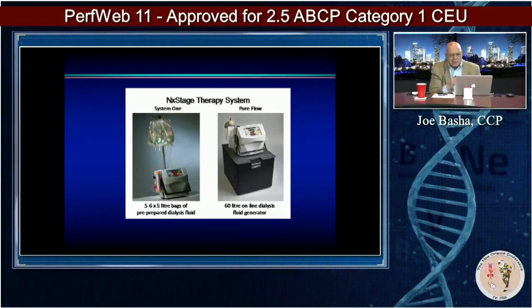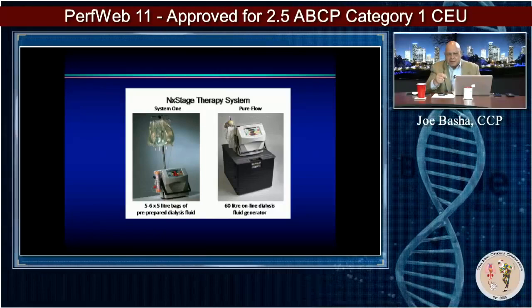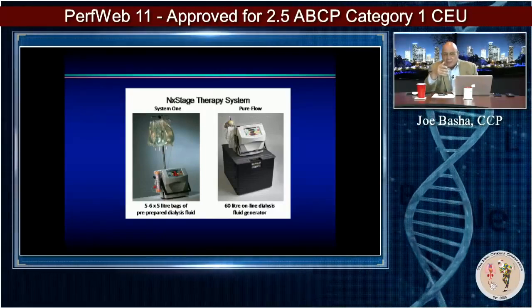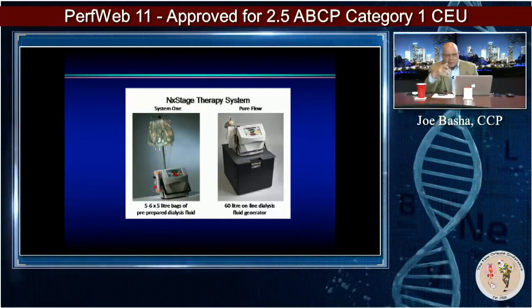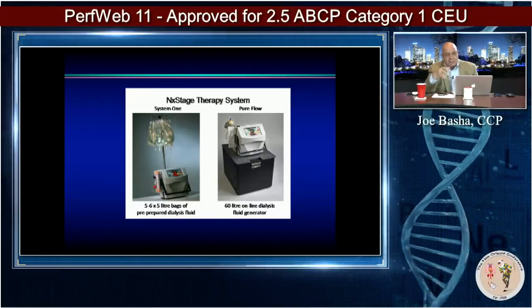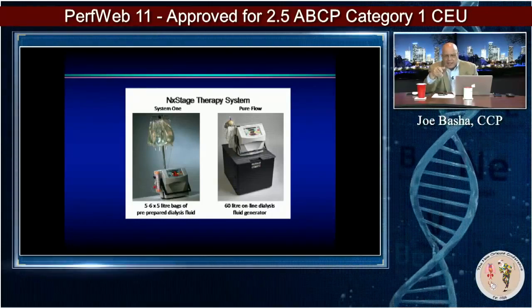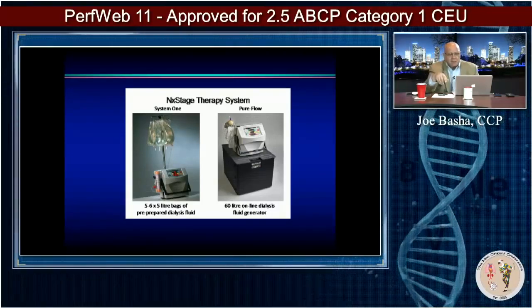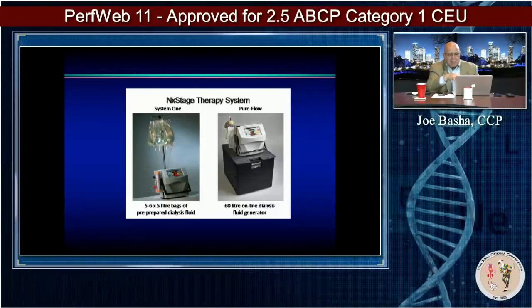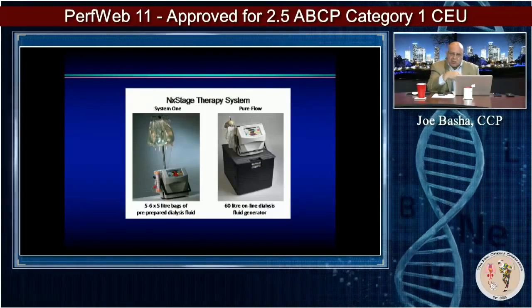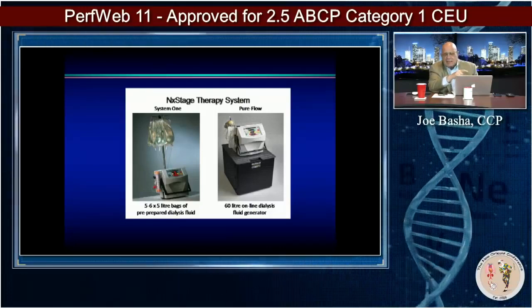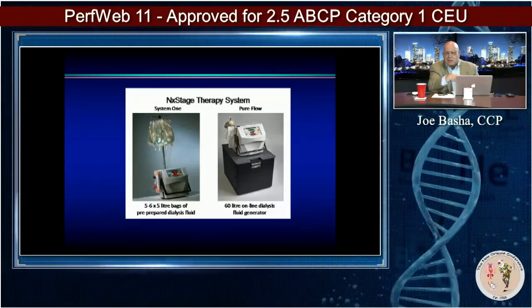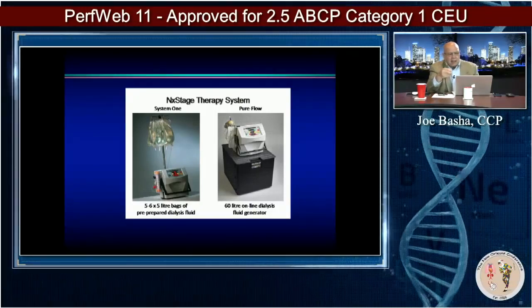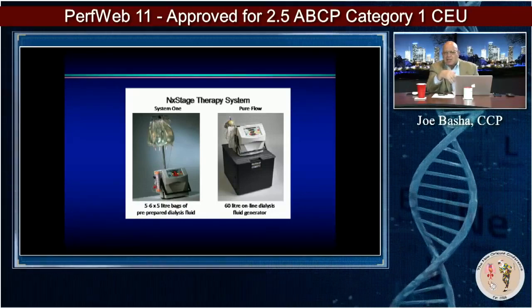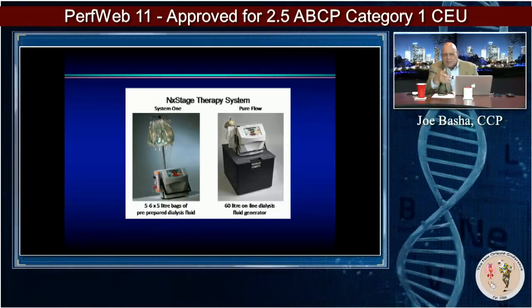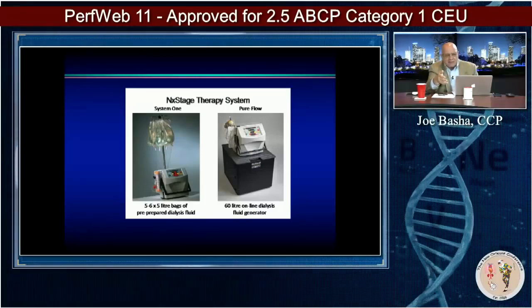It will do everything the other does, but this is volumetric, meaning each pump has a stroke volume, and it counts the number of RPMs and calculates the volume from that. Another potential advantage, which could also be a disadvantage, is that you put the waste into a sink, so you don't have to change the waste bags all the time. So it decreases the labor intensiveness of it.